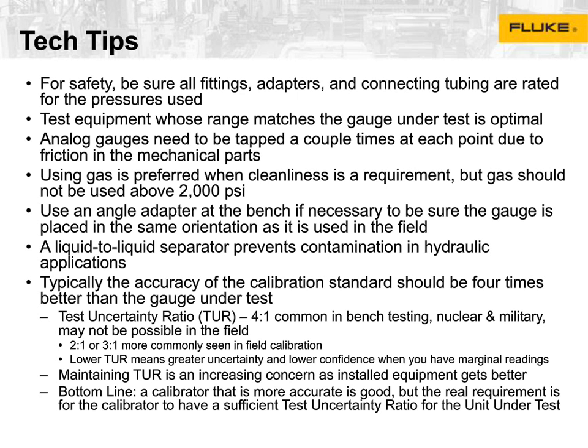Well, what's happened over time is that the units that we're testing have gotten both more accurate and less likely to drift or break. And so those requirements have been relaxed, and current best practice is about 4 to 1. However, that's not necessarily possible in the field.